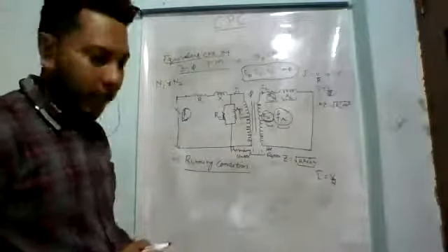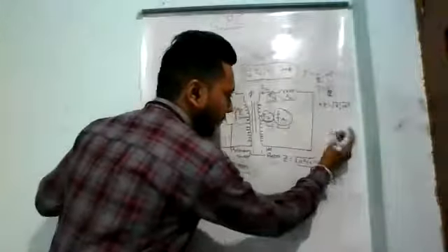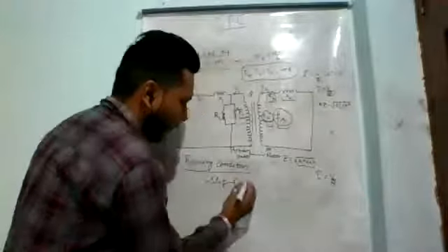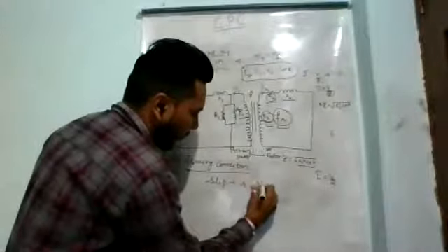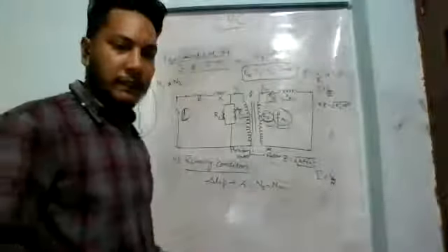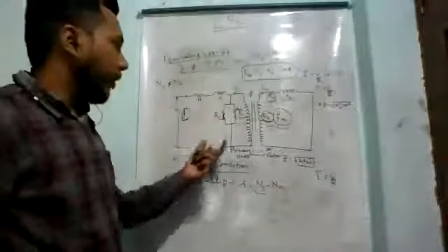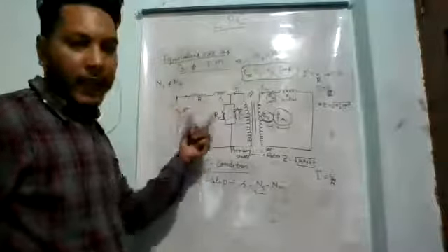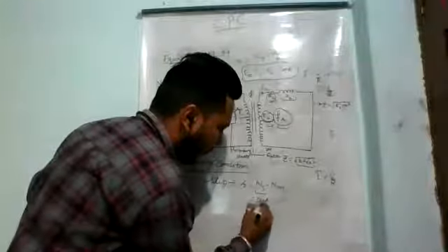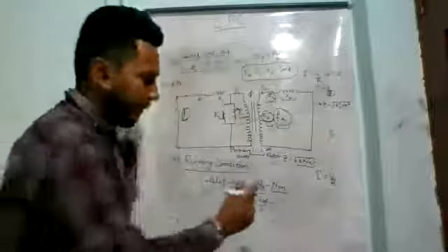When the rotor starts rotating, there is the existence of slip. Slip is nothing but the synchronous speed minus the motor speed, the shaft speed. Ns is the synchronous speed, which is the speed of the three-phase rotating magnetic field at the stator, and its formula is 120 f upon P. Nm is the shaft speed.